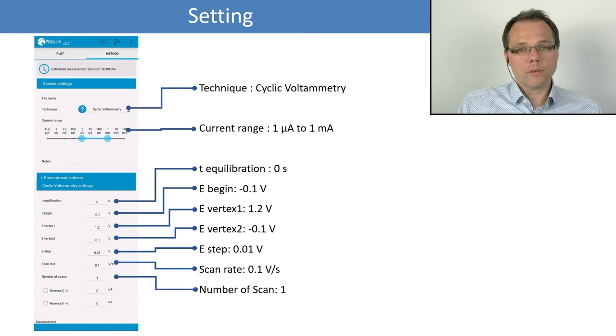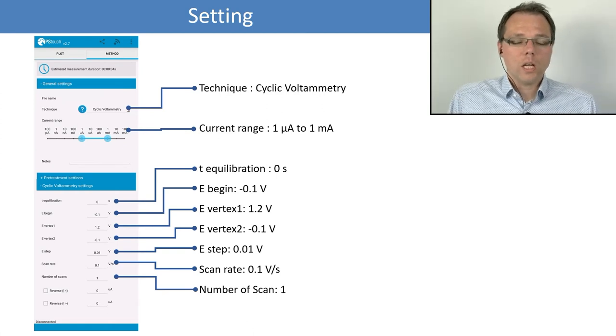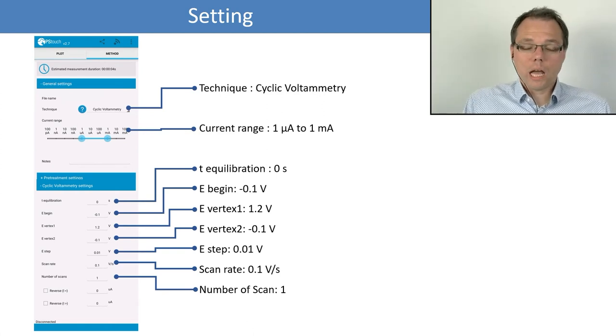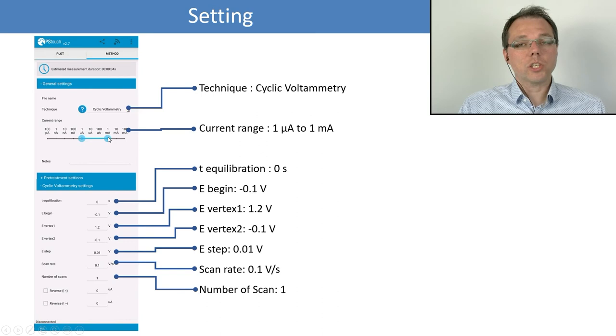At a low current range, you can measure low currents very well resolved. However, if you have larger currents, the potentiostat can't handle that anymore. Modern potentiostats usually have auto ranging, meaning you can choose multiple current ranges, just like here for the Sensit Smart, and the potentiostat will change the current range if it thinks that's necessary.